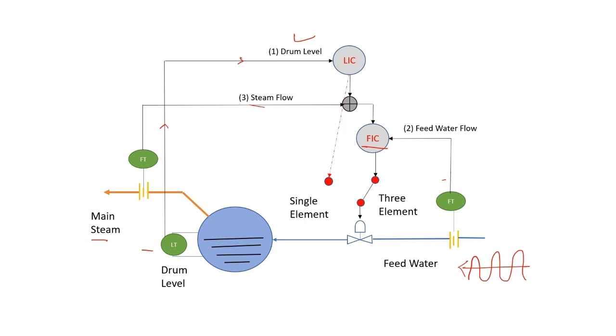The main steam flow can be added into the output of the level controller, and this combined output can go as a set point to the flow controller. Here the steam flow acts as a feed forward control load.